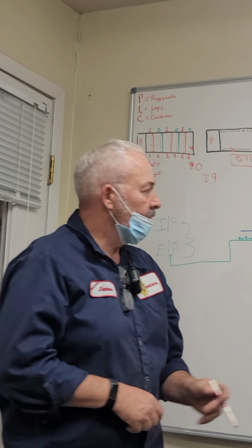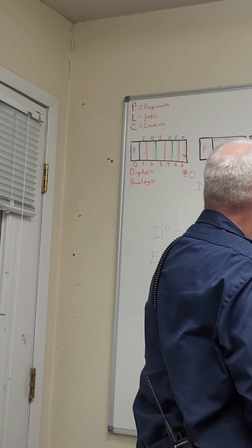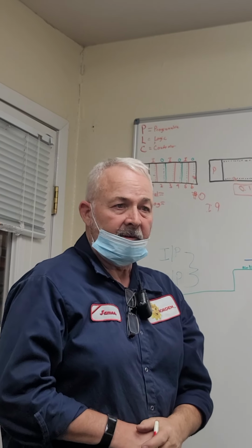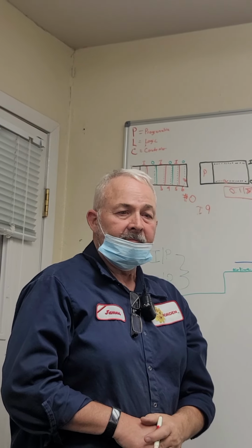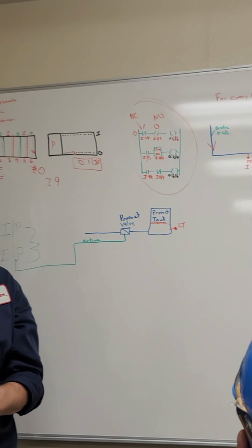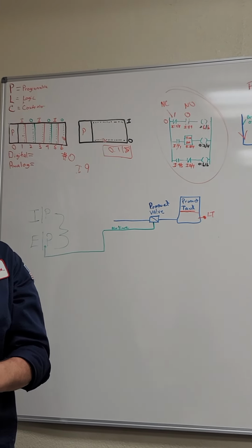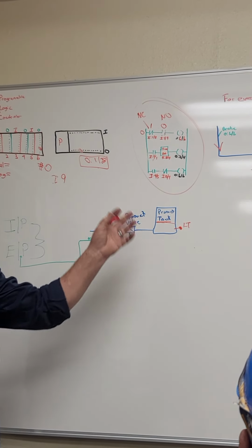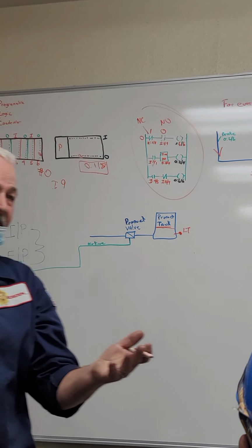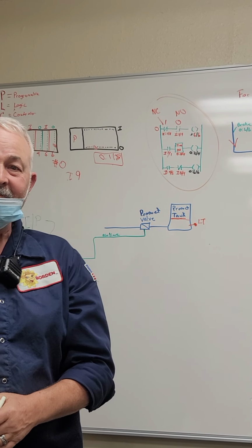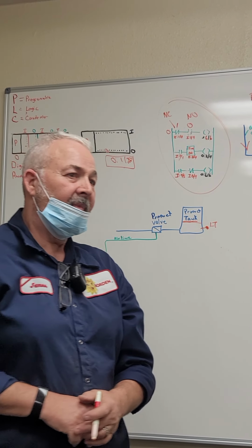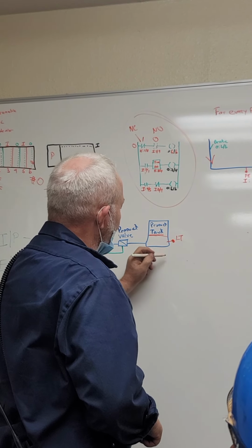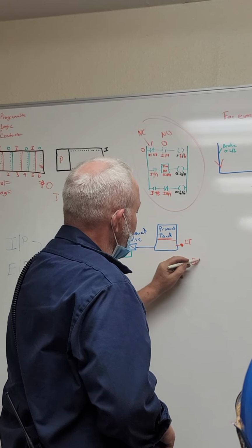So we have a level transmitter. What's it transmitting? Its signal. Air signal. Is it in its range from 0 to 100? It's measuring weight, it's measuring pressure. It's not measuring level. It's a pressure transmitter, is it not? But you say level because you say 3 inches to 8 inches or whatever. So our product tank is going to be from 0 to, let's just say, 20 inches.